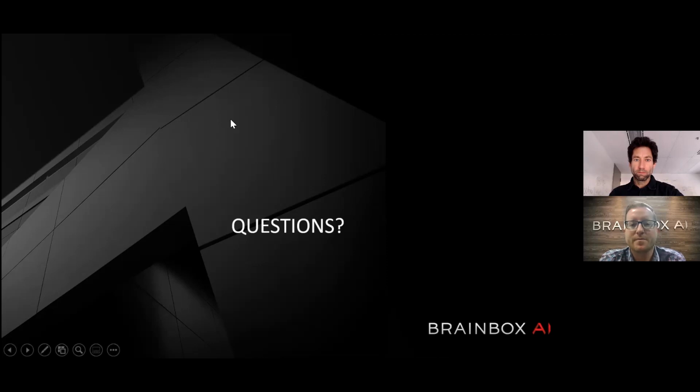Awesome. And that was the last question. I don't see any in the chat. Oh, wait a minute. You mentioned Haystack. What about Brick? Josh, correct me if I'm wrong. We are not using Brick today. We're just using Haystack, I believe. I would have to defer to the mapping team, but yeah, we're mostly using Haystack. I think we explored Brick, and it's a little bit newer protocol. From our perspective, we just have to normalize it to something. So right now, all of our algorithms and everything run off Haystack tagging. If a building already had Brick nomenclature, the translation to Haystack should be relatively quick and easy from our perspective, but we would translate it to Haystack.